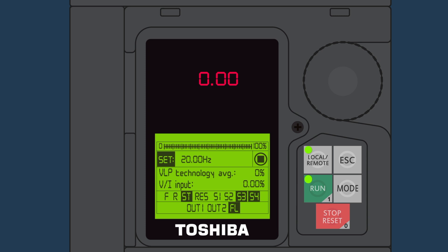Please note that if the LED is flashing off, this indicates that an emergency stop has been initiated from a remote source and the ST terminal is open. This cannot be reset from the Stop Reset button.